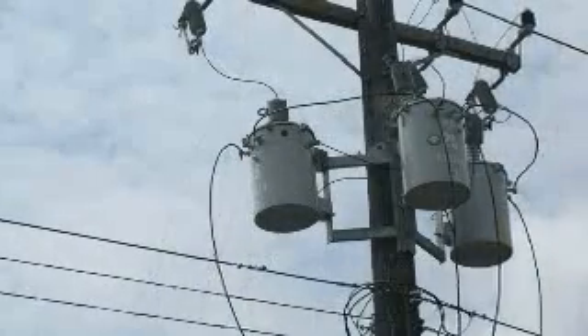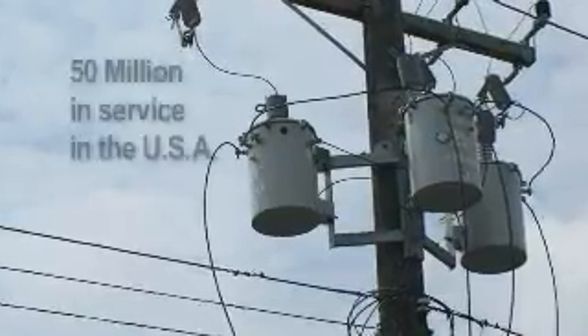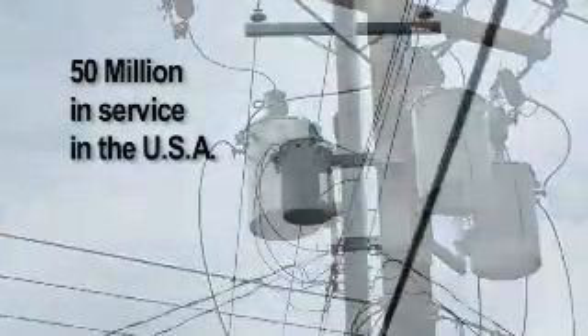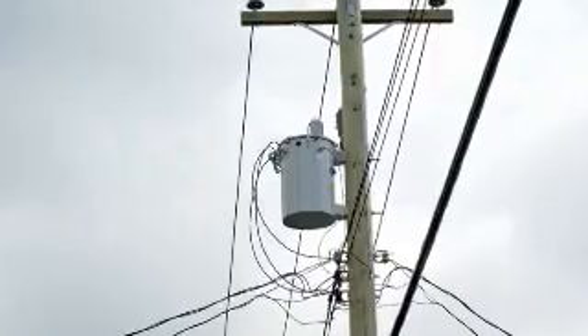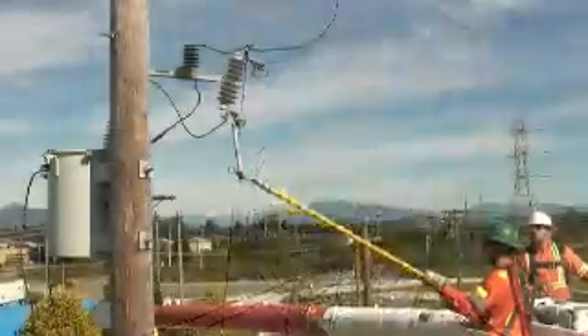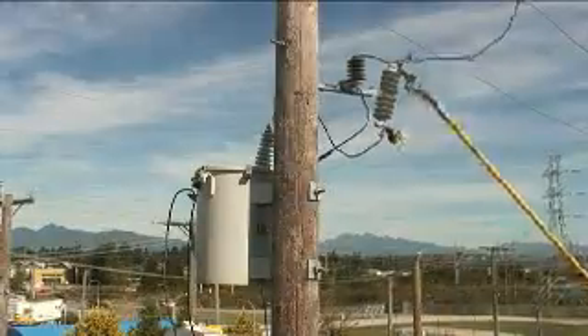Transformers. In the United States alone, there are over 50 million pole-top distribution transformers in service. Every year, 3 to 5% of them are re-energized, making it one of the most common operations for linemen. Lightning is the leading cause of transformer failures. Other causes include manufacturer's defects, mechanical damage, and different current-related failures.